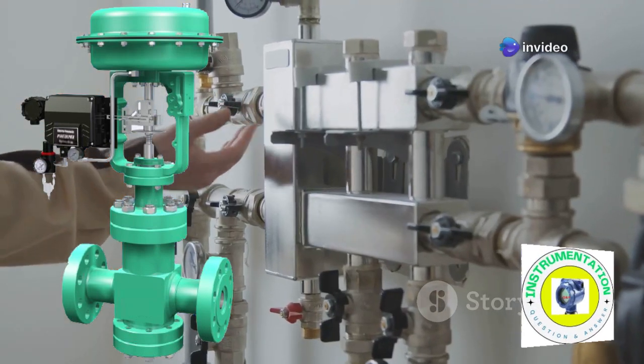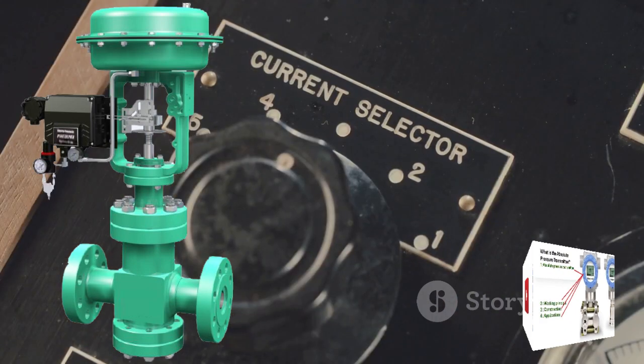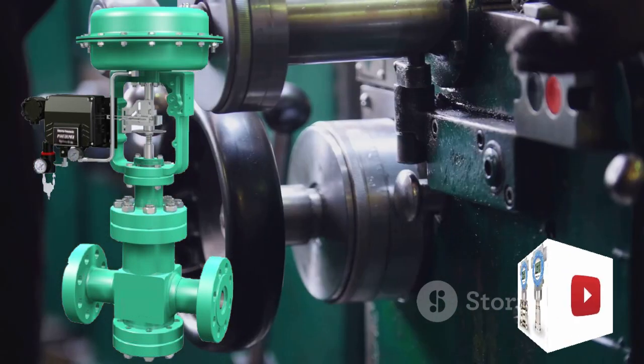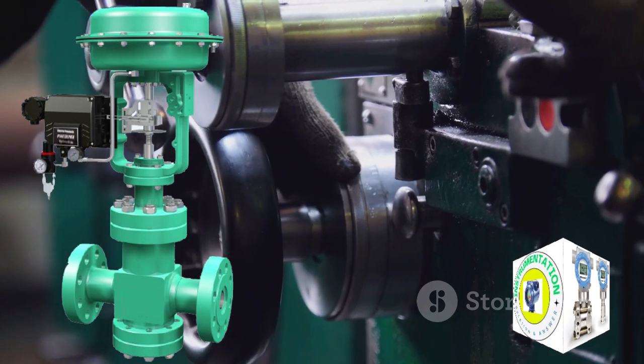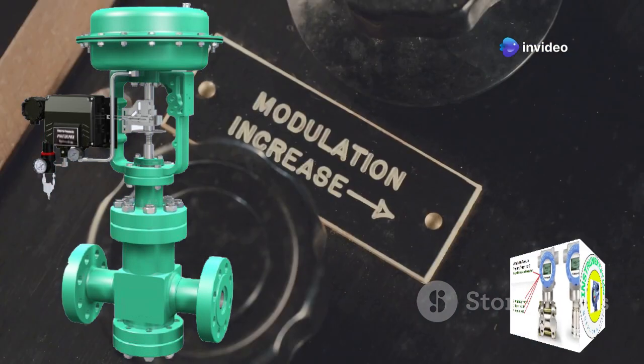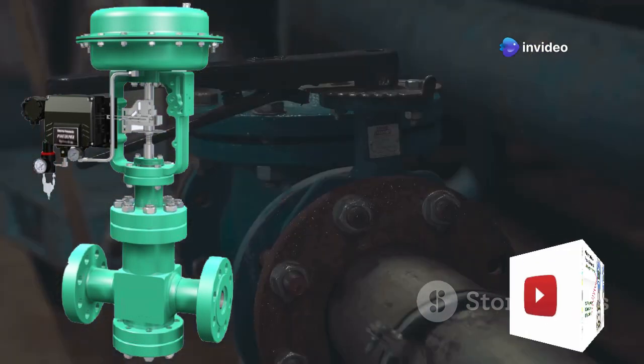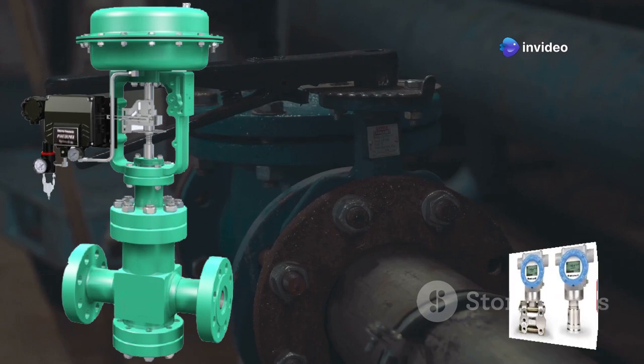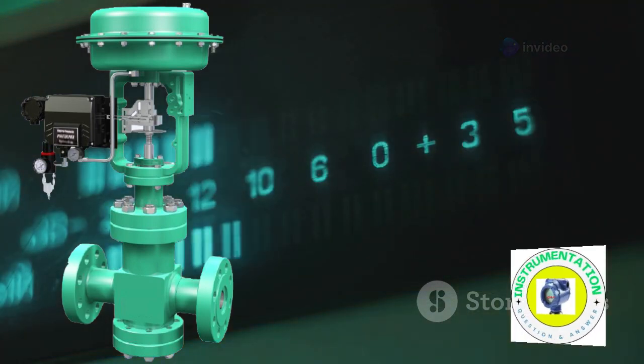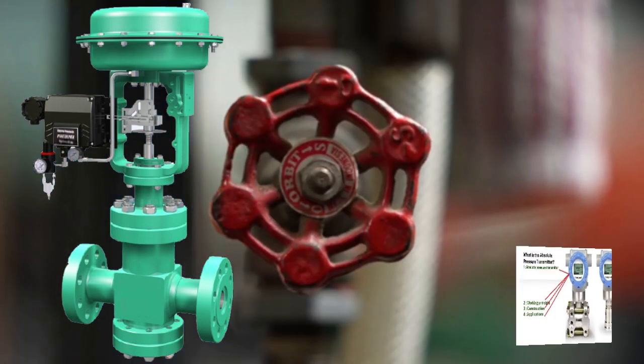That's when I switch to manual calibration. First, set your control signal to 4 milliamps. Adjust the 0 setting until the valve is exactly at 0% travel. Next, crank it up to 20 milliamps and dial in the span so you hit 100%. I always double check by setting it to 12 milliamps, should be right at 50%.